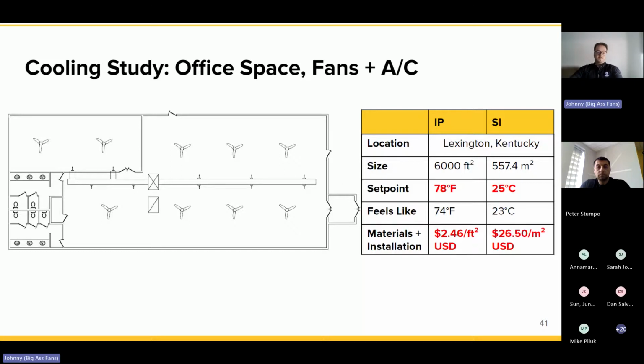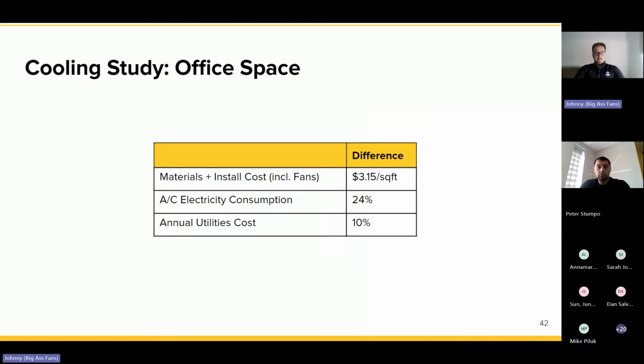Now you have individual workstations effectively with their own comfort zone because they can adjust the fan as needed. And again, we're saving on the materials cost pretty substantially here. So when we summarize, materials and install costs went down significantly. We know T-bar ceilings are not cheap. The install cost associated is expensive as well. So we're reducing that. We're opening the building up and we're using fans for D-strat and mixing. So AC consumption dropped by 24% and utilities costs 10%. So again, still some savings on the gas side in addition to the summer electricity costs.